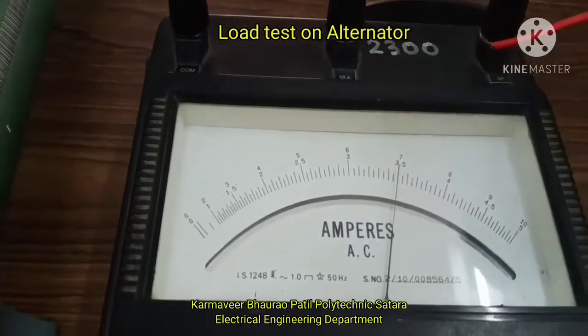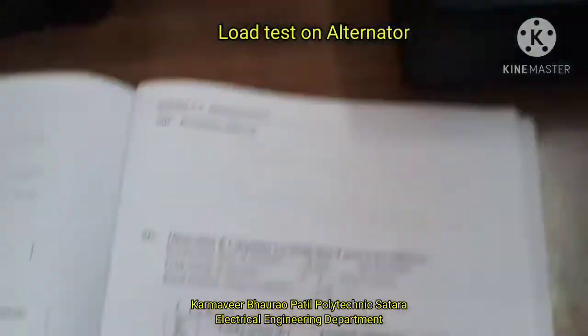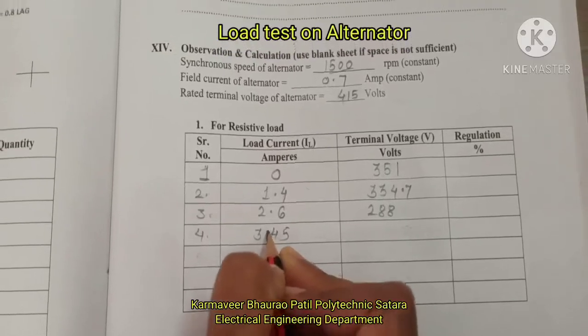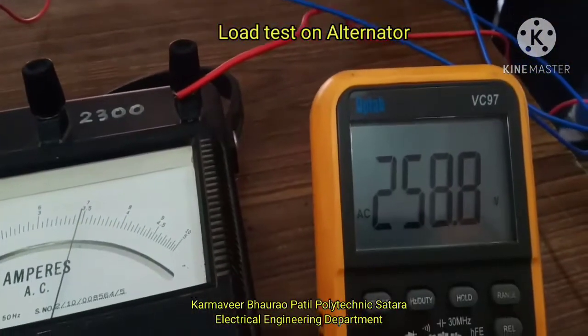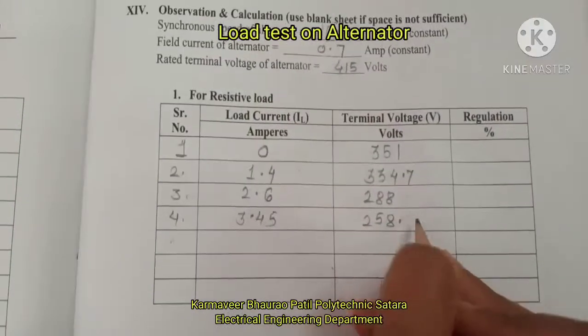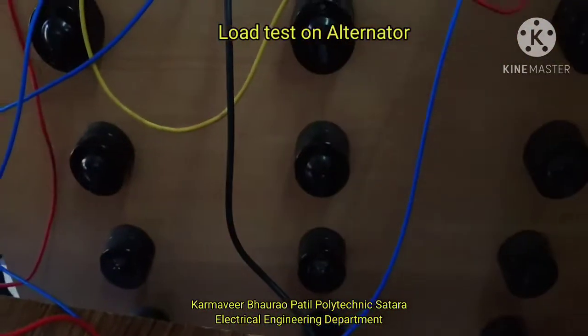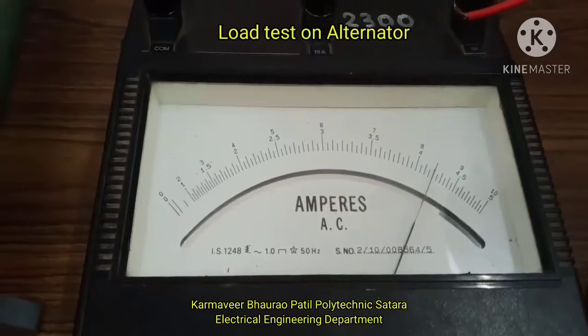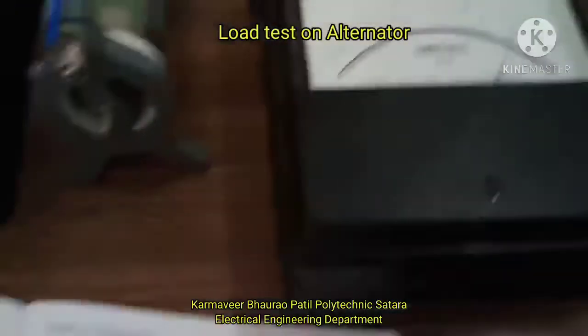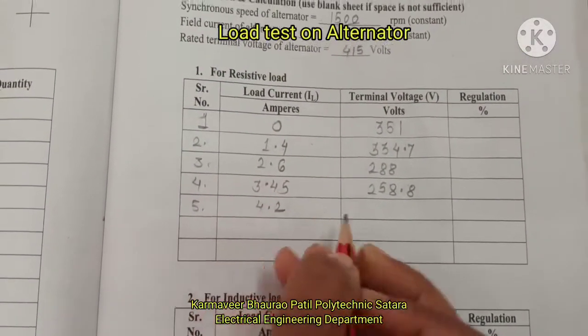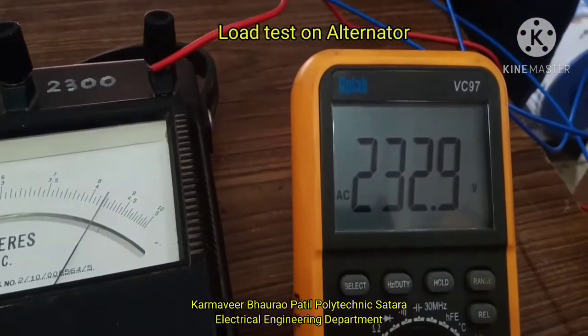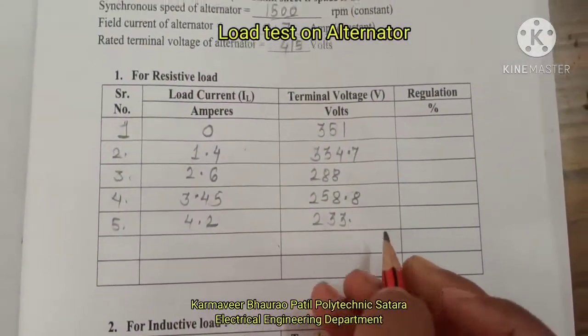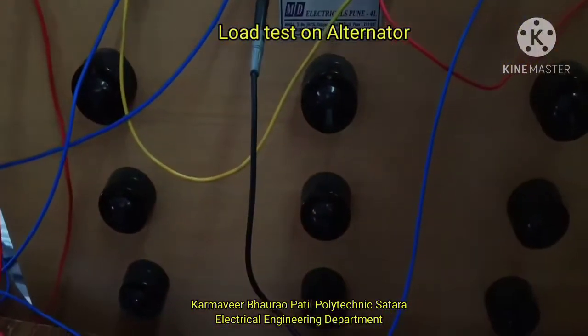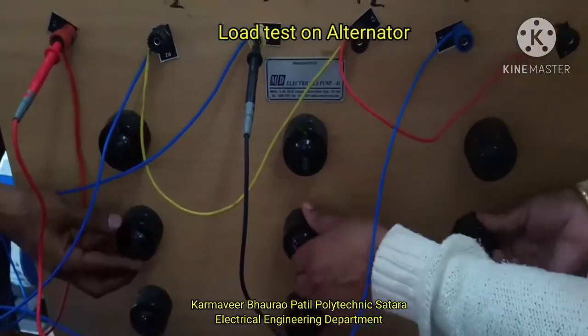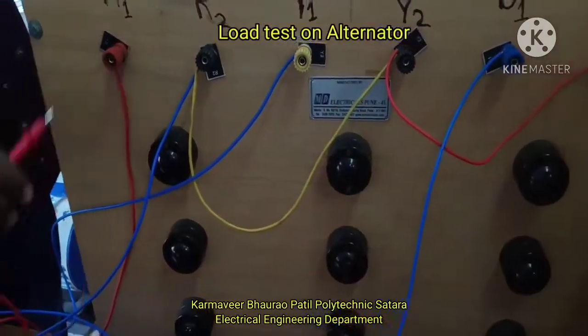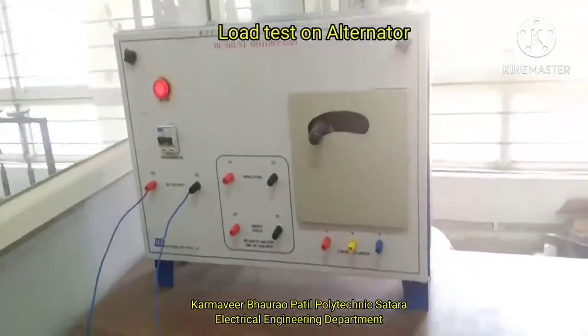One more load step: 3.45 current and voltage 258.8. And then the last reading, current is 4.2 and the voltage is 233 volt. So that was the last load. Now we'll make the load off. Then the alternator excitation is set to 0.